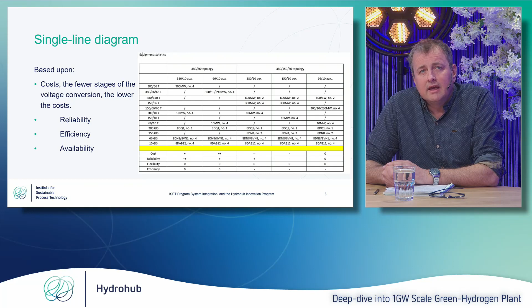Basically, the recommendation was that we go from 380 kV at the point of connection with TenneT, through a 380 kV three-winding transformer, to 66 kV, and then at 66 kV towards the rectifiers, the transformer rectifiers, and in some cases also harmonic filtering and static compensators. But Thomas, my colleague, will come back to that later, so I cannot tell too much, because otherwise Thomas has nothing to do.